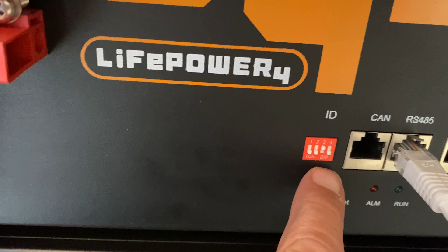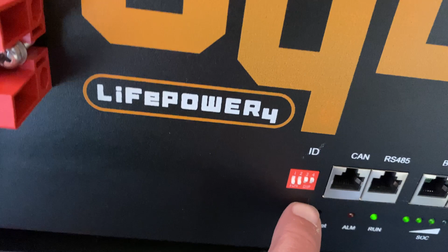Second important thing we found during the troubleshooting session to get things to work is that you do not want to set your battery dip switches so that pack 1 is enabled. You want to start with your dip switches at pack 2 — configuration 1 down, 2 down, 3 up, 4 down.